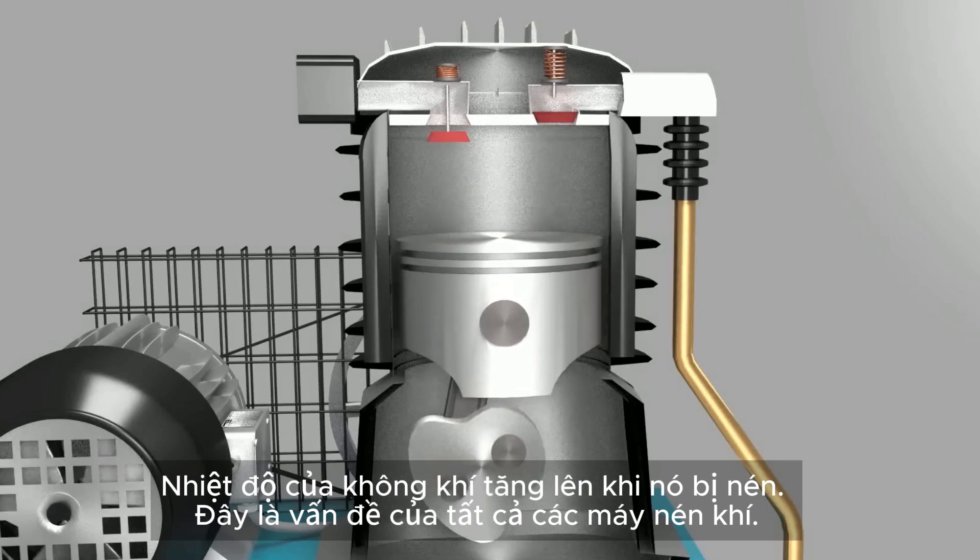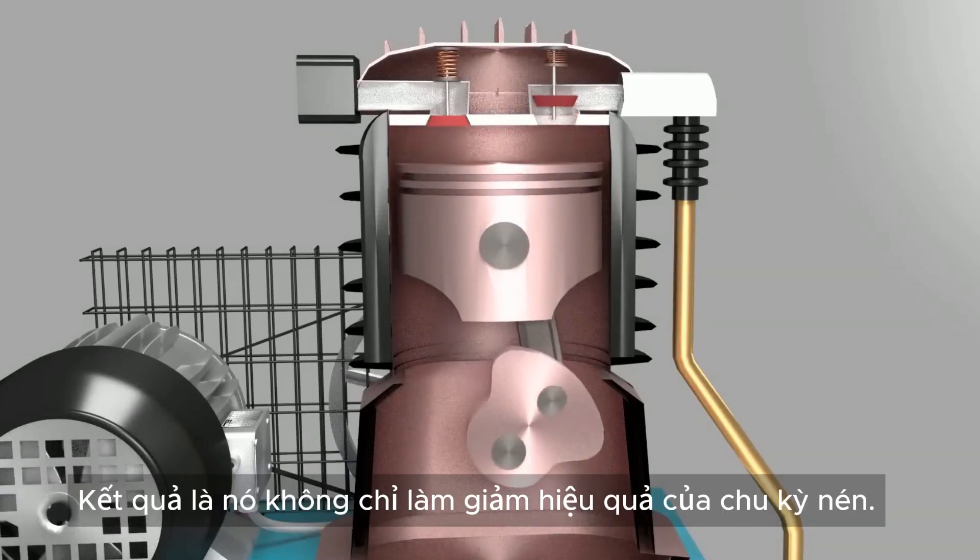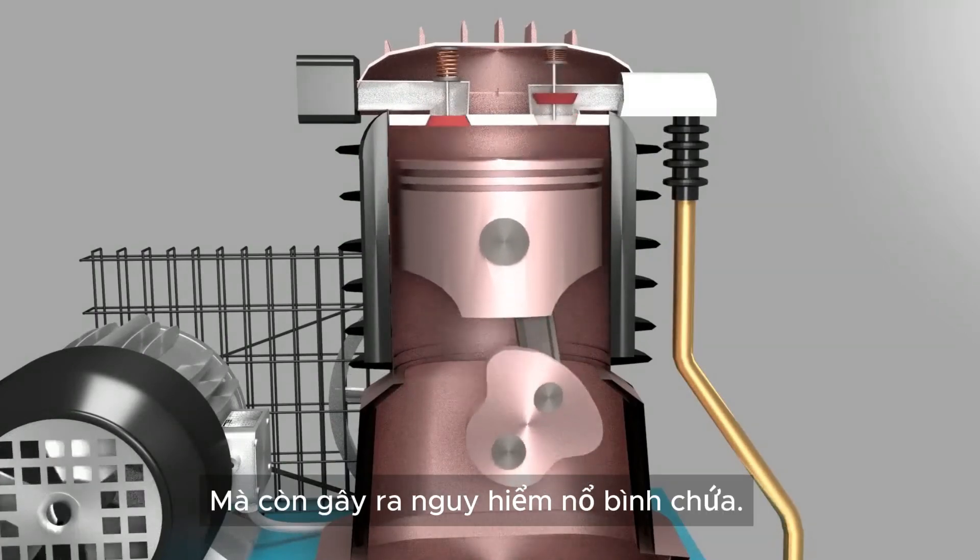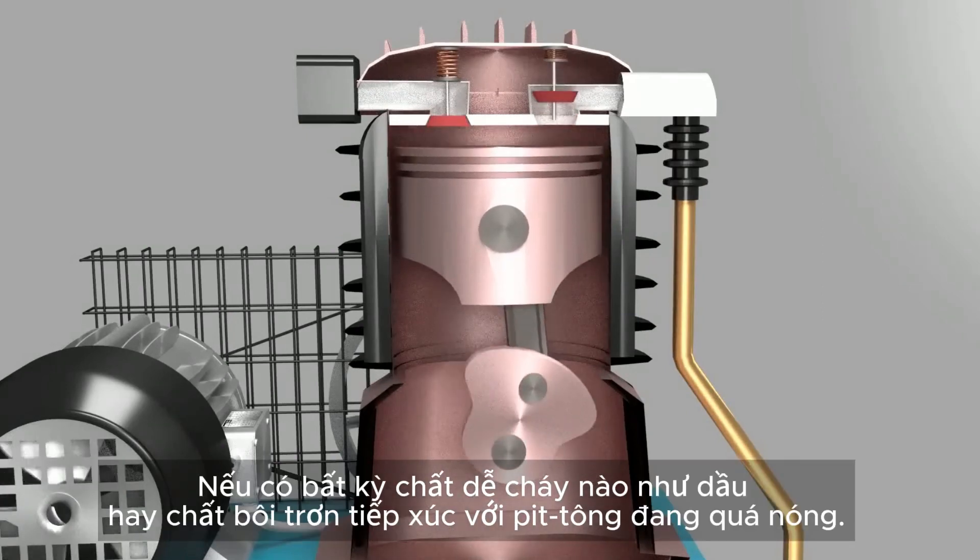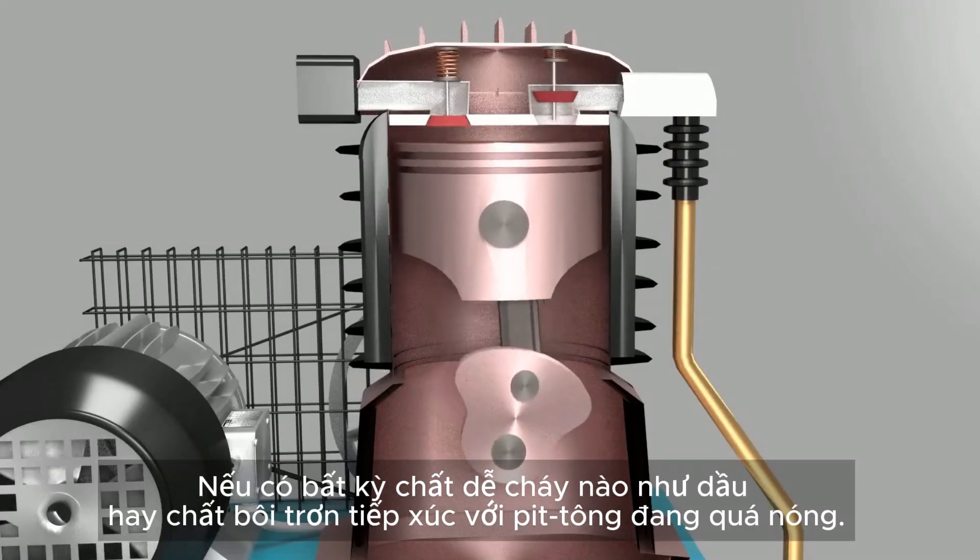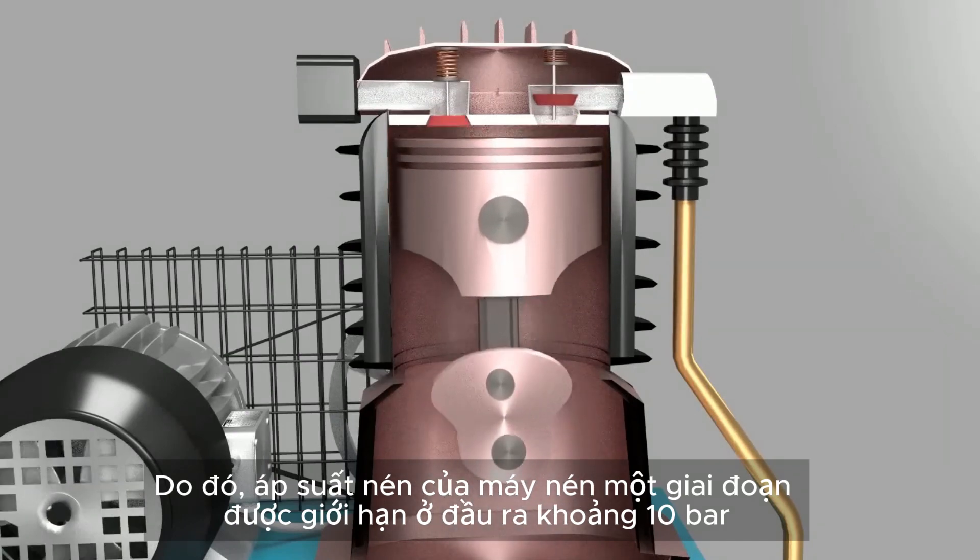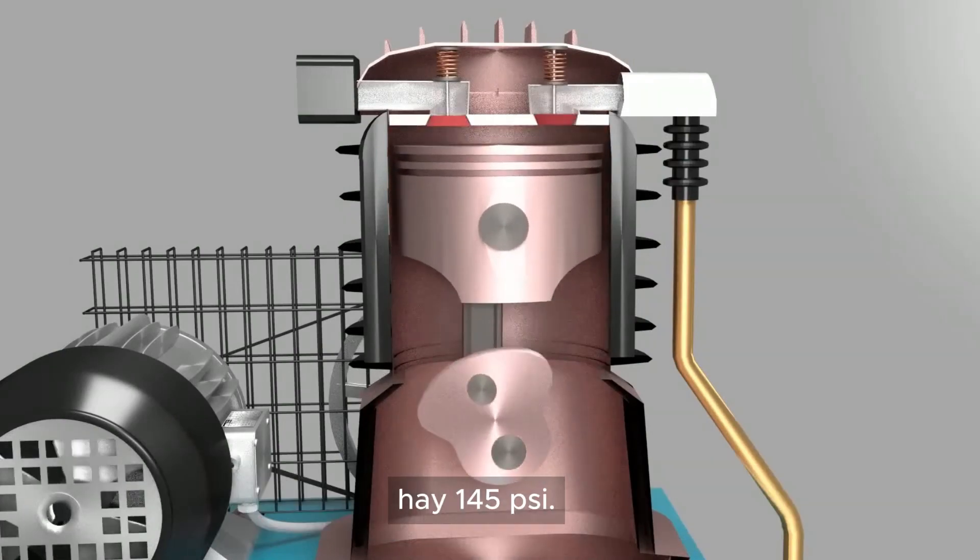Air heats up when it is compressed. This is a problem of each compressor. The result is not only a less efficient compression cycle, but also to a real danger of explosion if any inflammatory substances, such as oil or lubricant, get contact with the overheated air and piston. Therefore, the compression of a single-stage compressor is limited to an output pressure of about 10 bars, or 145 psi.